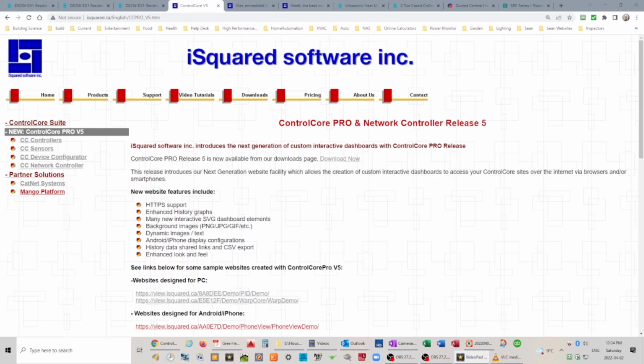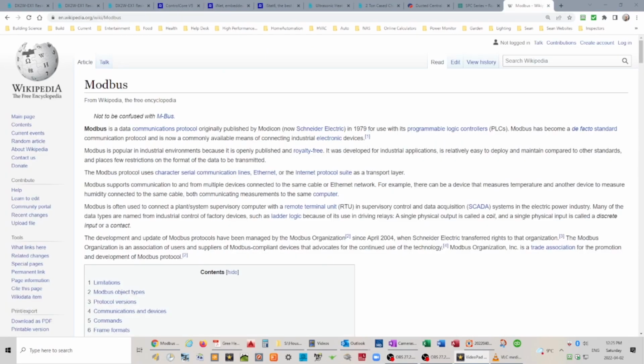The control of the system is via a software package from I2 Software Inc. called ControlCore Pro. This software communicates over a Modbus communication protocol and allows for the control of all parameters of any Modbus compatible device. Modbus is a data communications protocol that has become the mainstream go-to control protocol for industry. It communicates via serial cables, Ethernet, or IP.